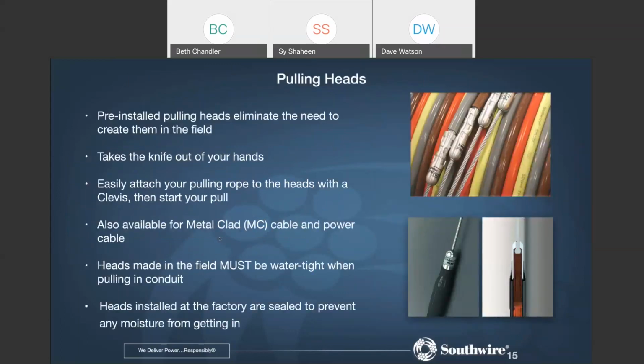I see that I'm getting into size time, so I'll hurry. These products are available with pulling heads from the factory. So rather than having to make up a pulling head at the job site for all the conductors, these pulling heads are applied to each conductor, and they are sealed to prevent any moisture from getting in, which is pretty important when you're pulling underground through conduit that probably is filled with water. These sealed factory installed heads are going to keep the installers from using knives. It makes it a lot faster because they can just take these, attach them to a clevis, and start the pull. And so it's going to save on labor, should reduce potential injuries, and keep the product properly sealed as it's installed. So next.